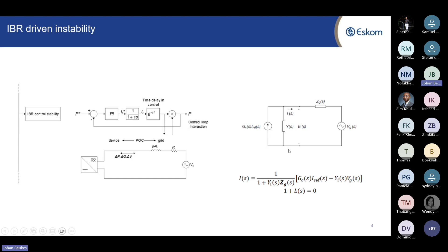So what it means is, with grid following inverters, you can start fighting yourself if that impedance becomes too high, because you change the voltage at the point of common coupling more than the grid changes it. And that typically happens when your short circuit ratio drops below 3. So that is a basic principle of instability when you have these purely inverter driven instability problems.